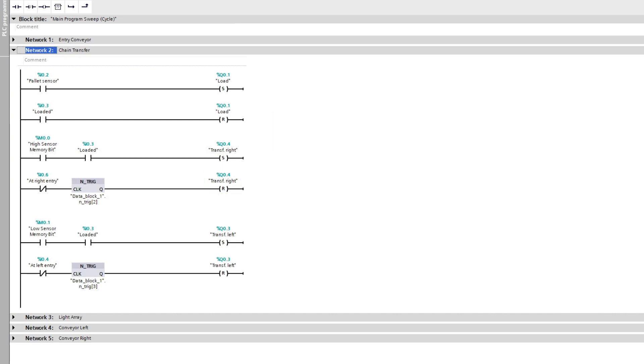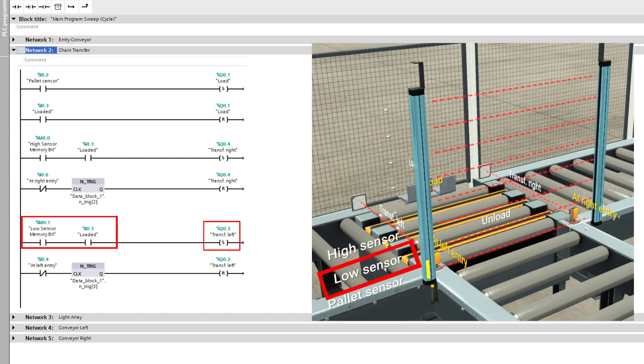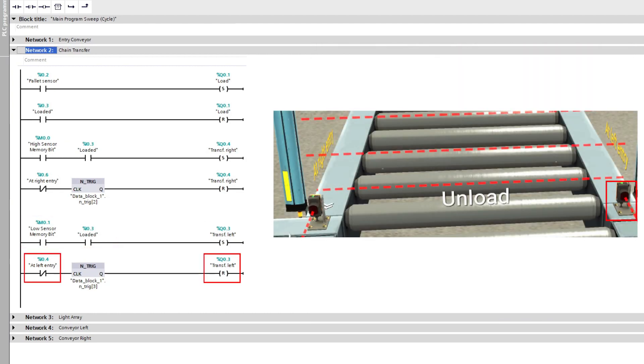And to make the pallet go left, it is pretty much the same thing. The only difference is that we want the signal from the lower sensor for a small box to let it go left. And it's the left sensor that will reset the chain conveyor instead of the right one.